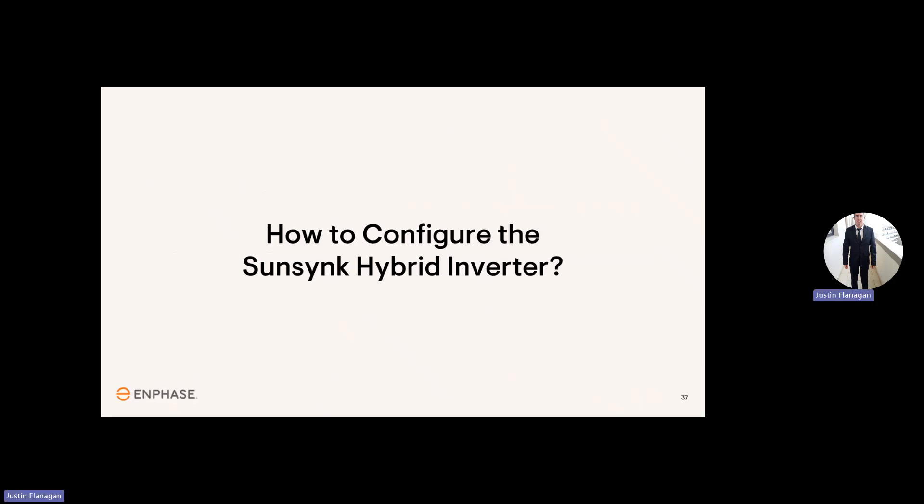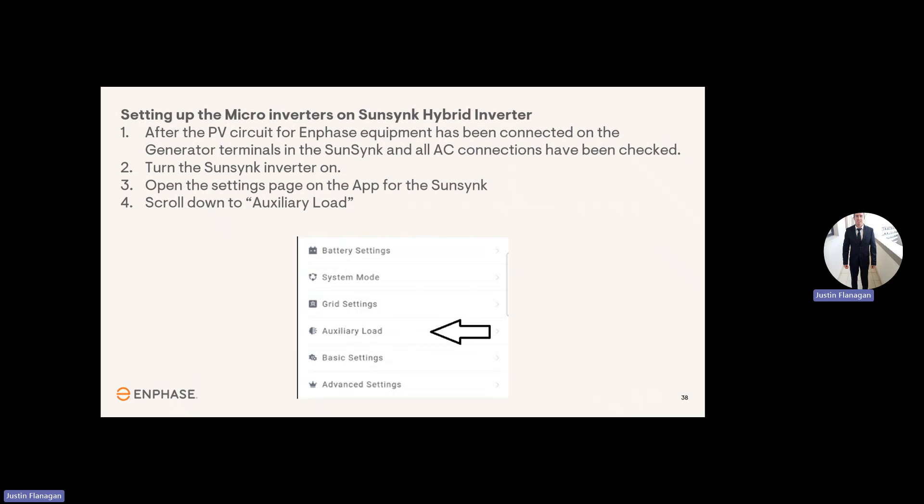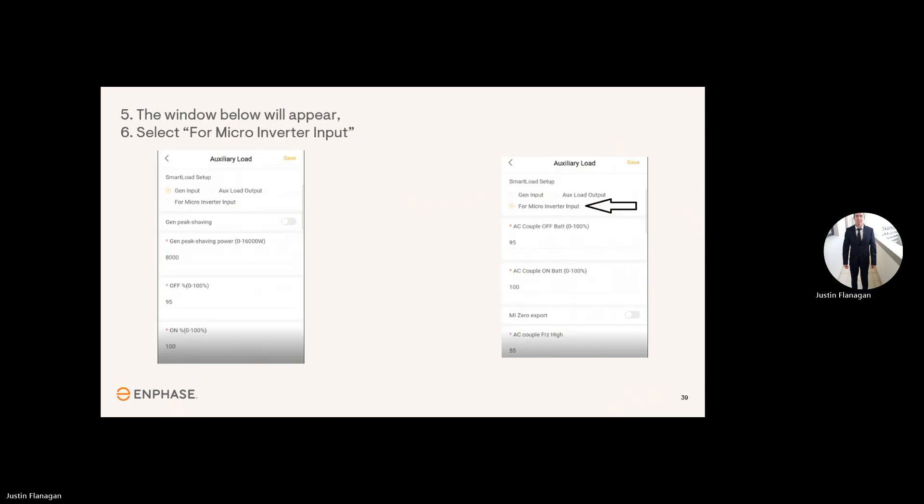How do you configure the Sunsynk hybrid inverter for Enphase? Setting up the microinverters on Sunsynk hybrid inverter. So after the PV circuit for Enphase equipment has been connected on the generator terminals in the Sunsynk, and all AC connections have been checked, turn the Sunsynk inverter on. Open the settings page on the app for the Sunsynk. Scroll down to auxiliary load. The window below will appear. So you'll see there the generator input has been selected. Now you need to select the one below it for microinverter input.